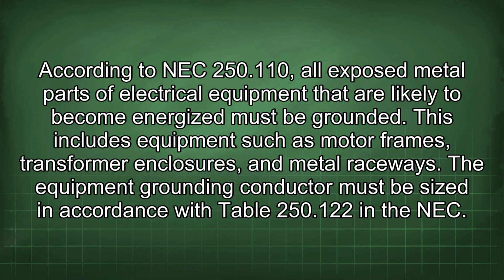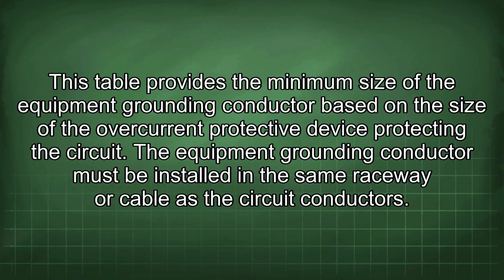According to NEC 250.110, all exposed metal parts of electrical equipment that are likely to become energized must be grounded. This includes equipment such as motor frames, transformer enclosures, and metal raceways. The equipment grounding conductor must be sized in accordance with Table 250.122 in the NEC. This table provides the minimum size of the equipment grounding conductor based on the size of the overcurrent protective device protecting the circuit.